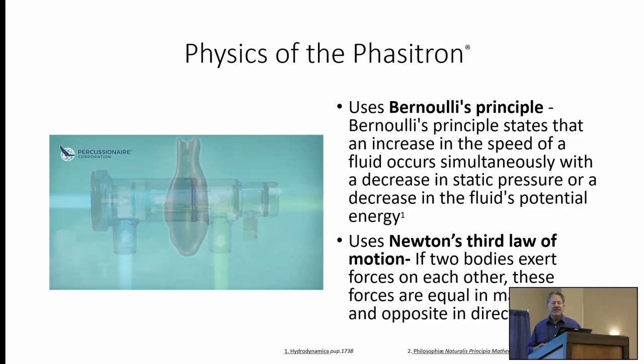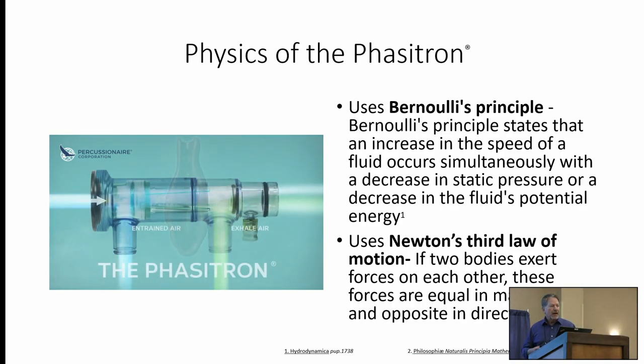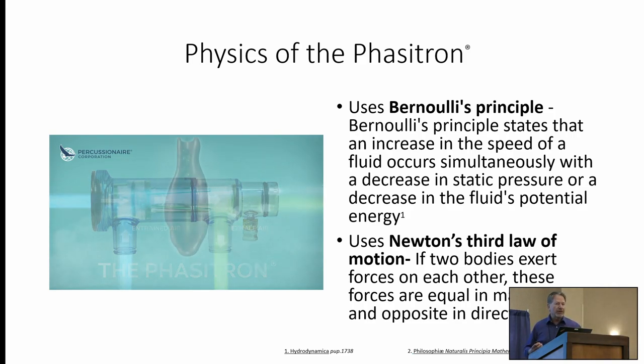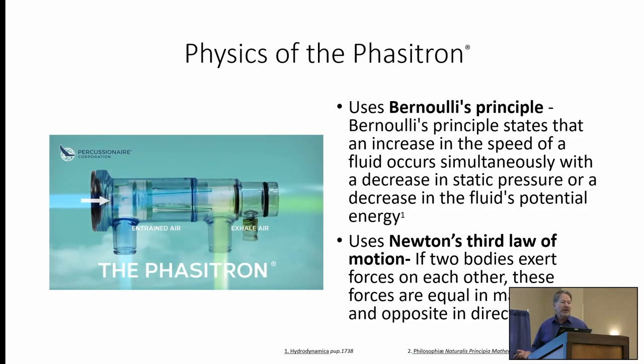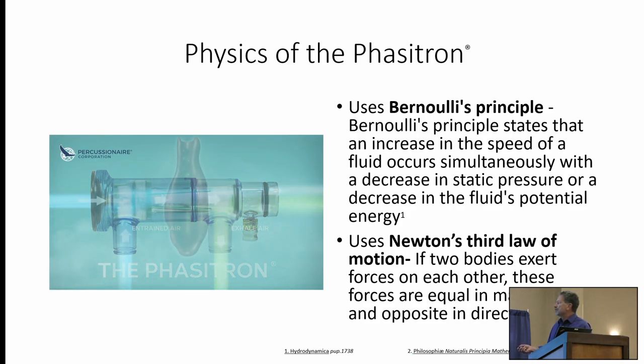Whether you're using it as therapy or as a ventilator, it reacts to resistance. So this device, whether you're giving a treatment to a patient with a mouthpiece or a face mask, or directly to an endotracheal tube or tracheostomy tube, it is not going to push a specified volume. It looks at the resistance or back pressure built up in the patient's airway or their mouth, and this drive flow slows down because of the Bernoulli effect, that an increase in the speed of fluid occurs simultaneously with a decrease in static pressure or a decrease in the fluid's potential.